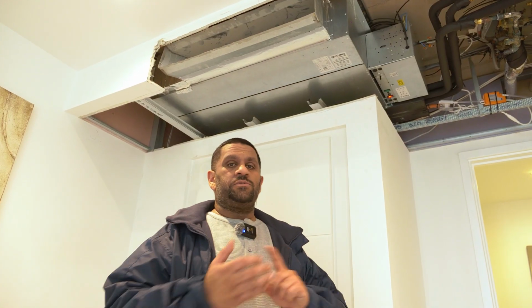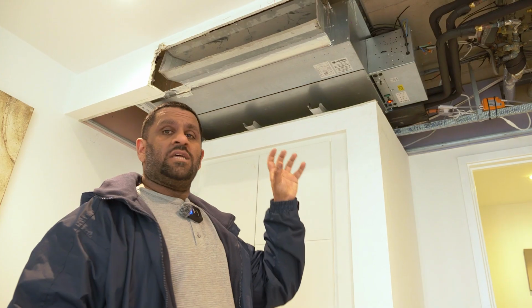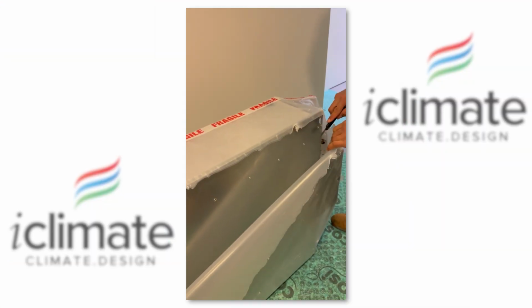We found out that the heat exchanger had been compromised and was leaking essentially. We deemed that unrepairable because we don't want to carry out repairs we cannot warranty, especially in a block of apartments like this. So we had the task to find a new fan coil unit. The old fan coil unit was manufactured by CIAT, which are not a UK manufacturer. If you've been within building services, you'll have heard of CIAT. They make lots of heat exchangers and cooling related products, but they are very hard to get hold of and technical support is near to non-existent here in the UK. We were tasked with finding a replacement fan coil unit that integrated into the existing services and also physically fitted within the bulkhead space. 6 weeks to manufacture this.